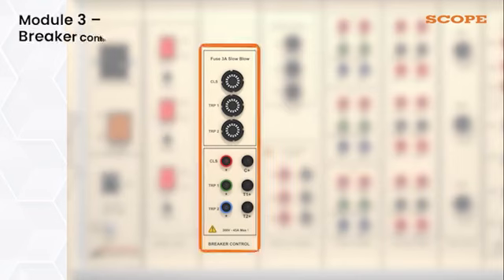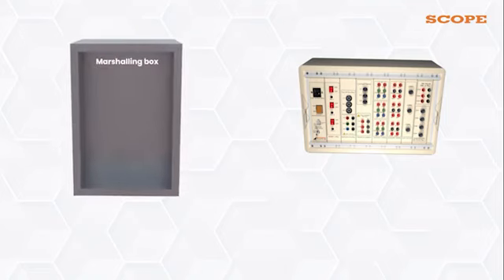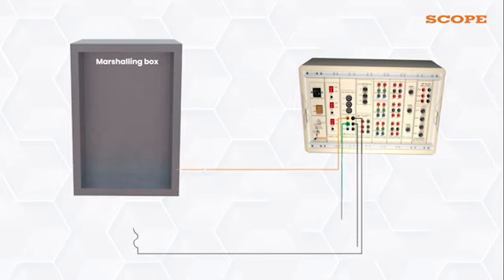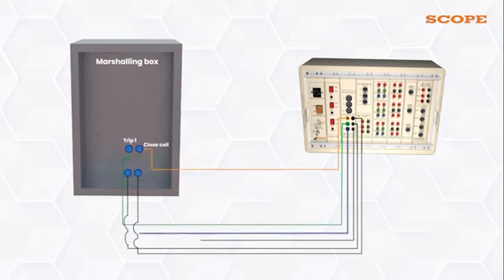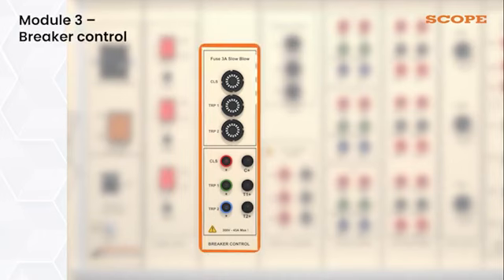Module 3 Breaker Control Module. For testing of circuit breakers, we need to operate the breaker through the instrument. For this, we have to extend the DC positive to the close and trip coil of the circuit breaker, and this is controlled by this module. This DC positive voltage is routed through the fuse to protect the short circuit or damage of coils. To test breaker operation through the kit is of utmost importance. To achieve the same, we use breaker control module.